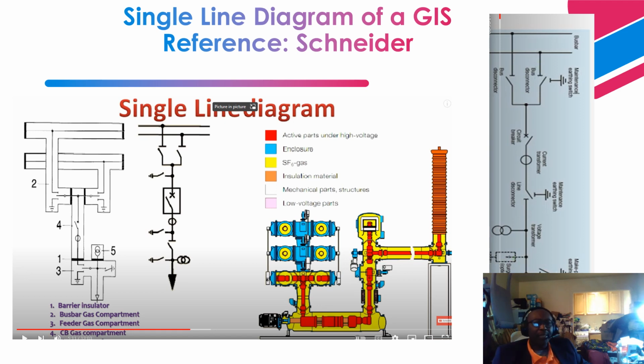Okay, so basically, like on the previous slide, right, we went through a double bus arrangement. Okay, so this is a bus, right? It is in an enclosure. This is the enclosure. All this enclosure is filled with SF6 gas. Similarly, this is the second bus, right? Inside the enclosure, it is filled with SF6 gas, right? So, the SF6 gas, what does it do? It's basically creating an insulating medium and also a dielectric strength to basically insulate the live component and also to interrupt any arcing that will occur in the enclosure, right?